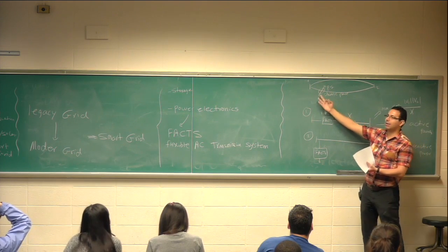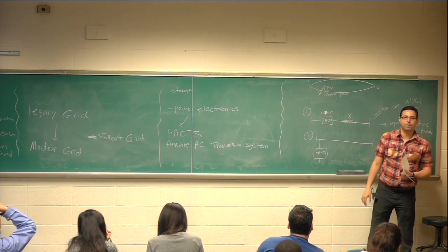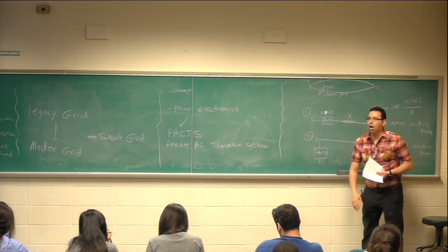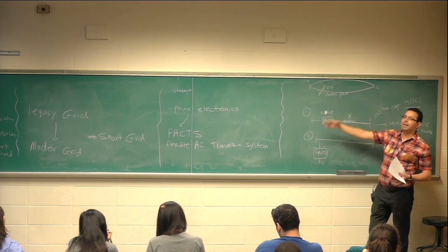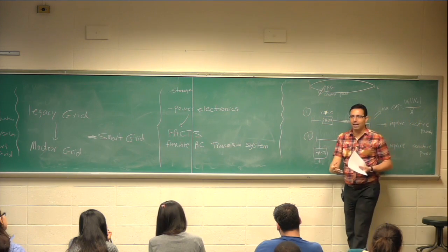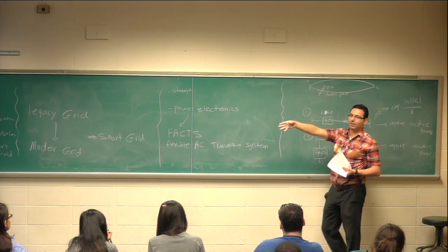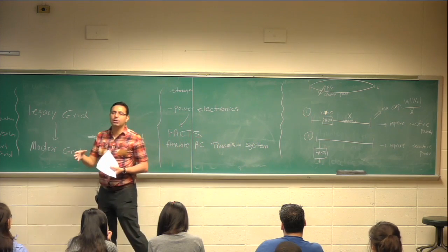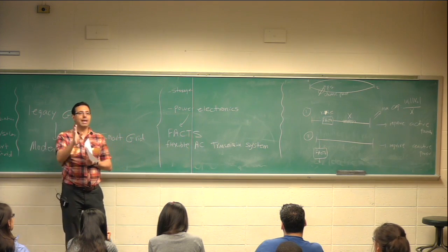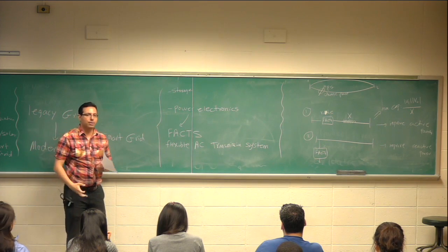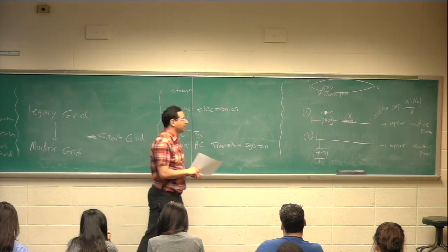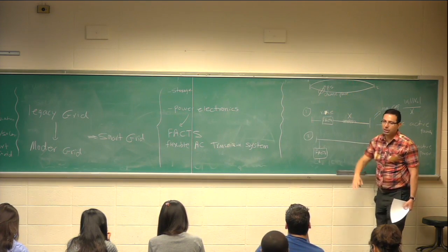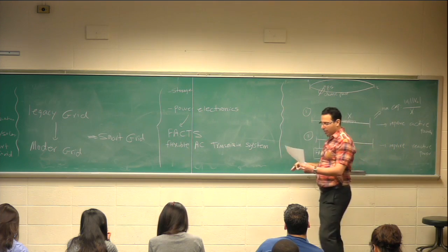But this is very expensive. Doing this is very expensive. And a part of expense comes from the following. Maybe the device costs like $4K, but installation in Manhattan could cost $30K. How can I install this here? We need a blackout. So if there is no blackout, they cannot install it on an active line. If you're using an active line, you cannot take it out and install this. You have to have the resources aligned around it. So there is a cost for buying the device, making the device, and there is a cost for installation. But we're going to see a lot of these devices.